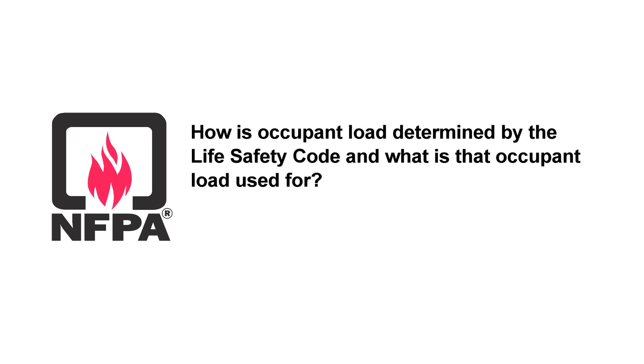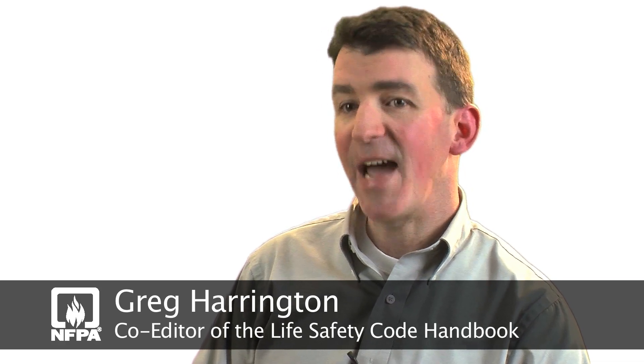How is occupant load determined by the life safety code and what is that occupant load used for? Occupant load in the life safety code is determined by one of two ways. The first way is you can determine your occupant load based on factors specified by the code — occupant load factors given in terms of square feet per person or square meters per person — and you would apply that factor based on the use of the space over the area of that building or portion of the building.